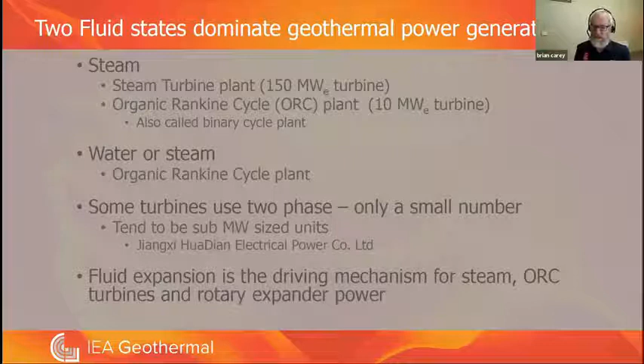I'll just talk briefly about a steam turbine for a little bit. So your steam is entering your turbine and is expanded through the turbine, and normally you have a condenser associated with your turbine, and the reason for that is that by running the exhaust of your turbine at subatmospheric conditions, you will generate more electricity. So for a turbine which is running at relatively low pressure, say an inlet pressure of 5 bars or 0.5 megapascals, you will basically double the output of that unit if you have a condenser online than if you don't have a condenser installed in the power system.